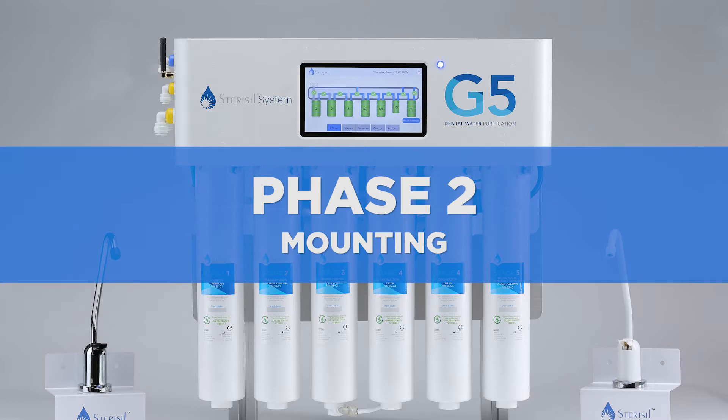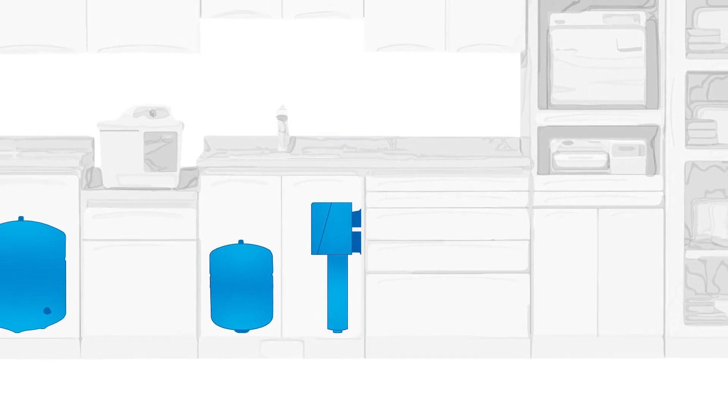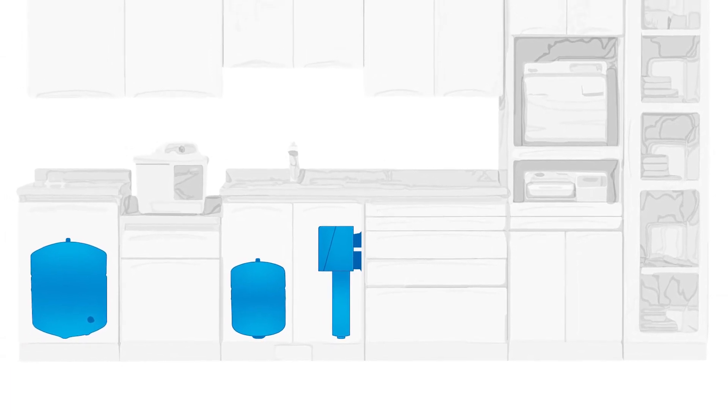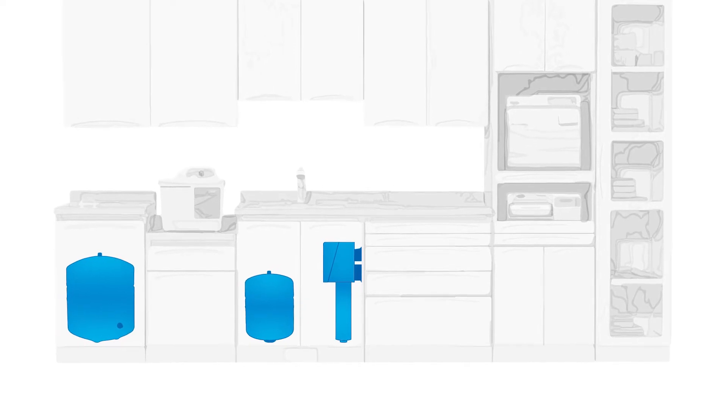Phase 2, mounting. The Sterisil System G5 can be installed nearly anywhere in the typical dental, medical, lab, or hospital setting, typically near a faucet and sink. The system and tanks are designed to fit under a countertop but can be installed anywhere there's a quality cold water supply and drain connection.